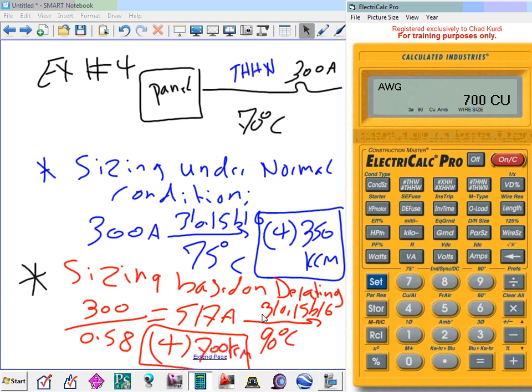The reason, and you guys have done it before, I don't take a conductor and derate the amps. You guys have done that with Gary. Take a conductor, multiply by 0.5, 0.6, this is how much amp I can do. That's not what we start with. We start with a load, up the amps, go size the conductor. So that's what you're going to be doing. If I give you a conductor right now, Chris, and I say, this conductor can carry 50 amps on a 90, and here's the derating factor, 2. What do you do to find how many amps you can pull out of it? Multiply and find the answer.